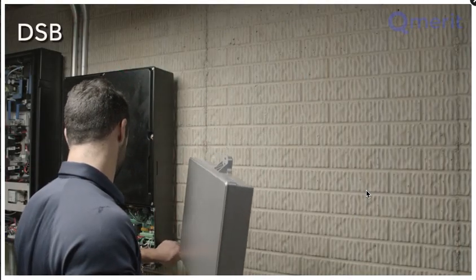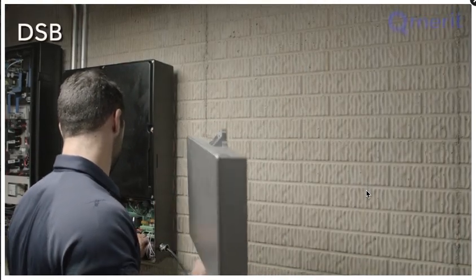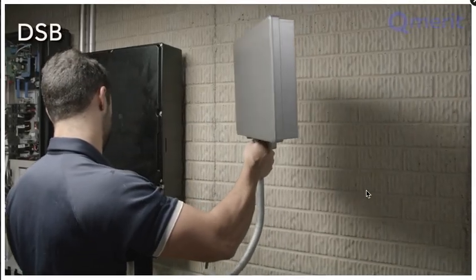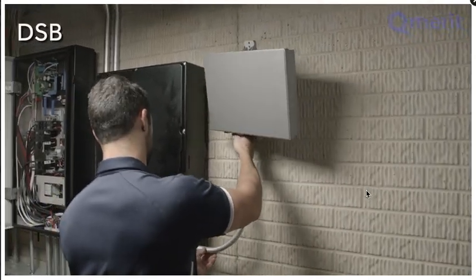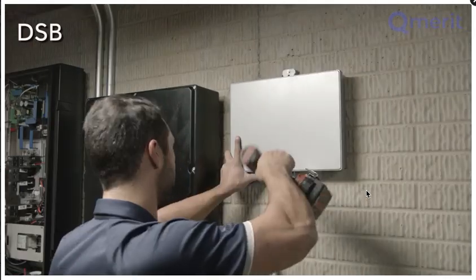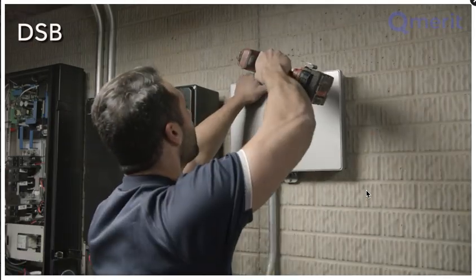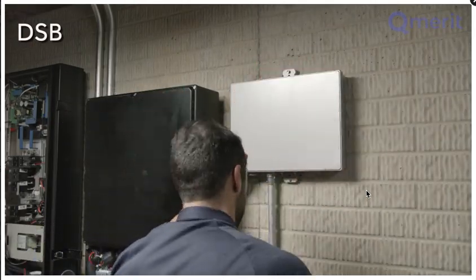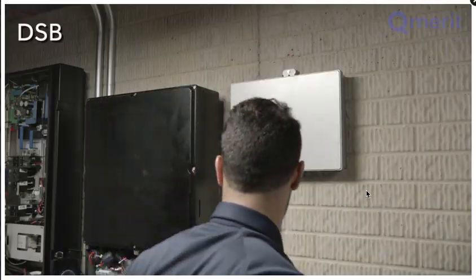Install the dark start battery, or DSB. This sits to the right of the bidirectional inverter. Make sure you mount the dark start battery no less than 3 inches away from the DBI. Stay close to ensure enough cable is available to complete the wiring.